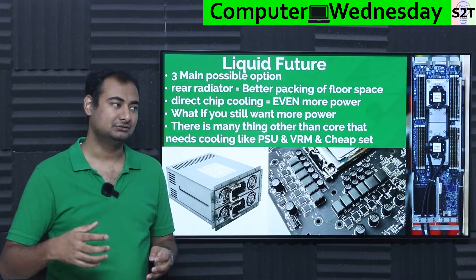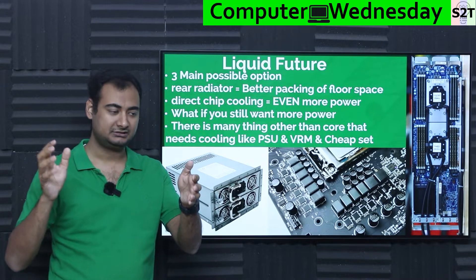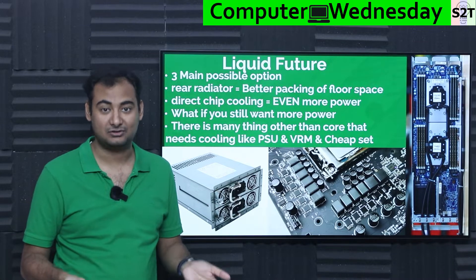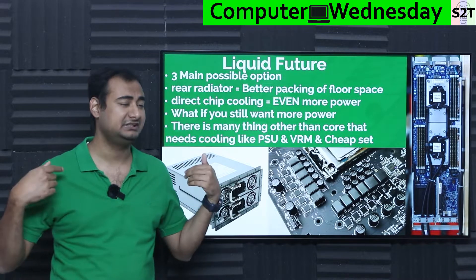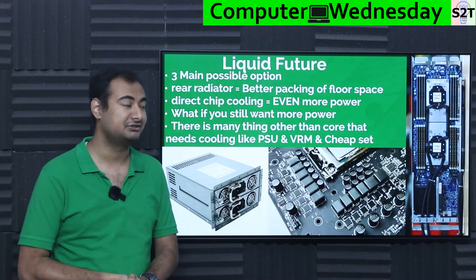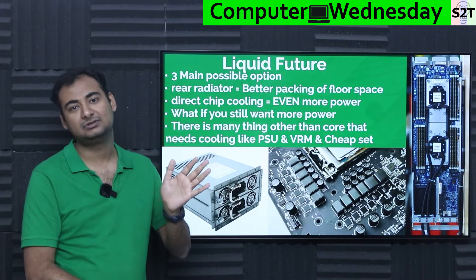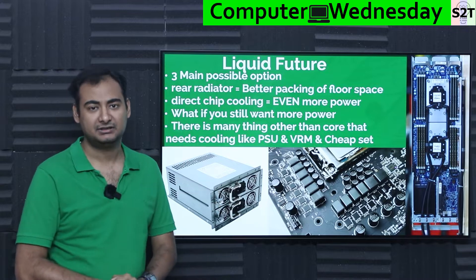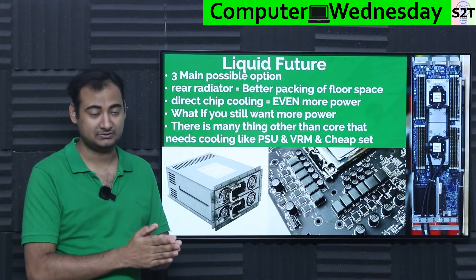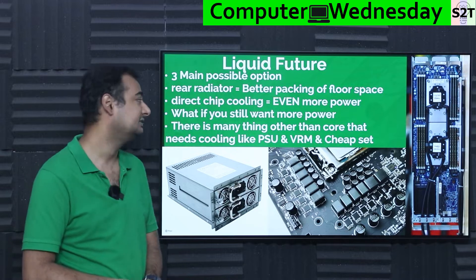Generally you cannot just have AC and cool the hell down — your servers would still be hot, because air is not a very good conductor. Consequently, you could literally have racks of servers where one server is creating hot air and dumping it into another one, and that other server is like receiving already-hot temperature, trying to cool itself down, fan goes berserk, and the air conditioning isn't convecting efficiently enough. Rear radiator solves that because it puts a giant water-cooled radiator just behind the server — all the hot exhaust gets cooled at the closest point possible, no modification required. Many supercomputers use this; it's very cost effective.